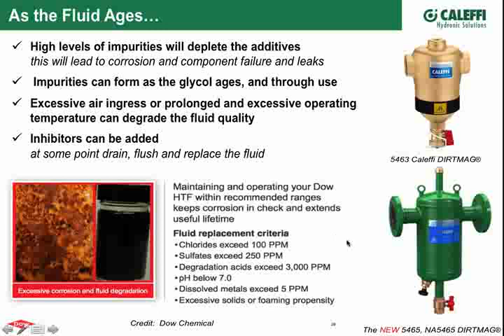This next one is that it's harder to get the air out of a glycol, and this hit home for me. I was at a trade show a while ago, and they had a clear tubing display of an air elimination device. I noticed the fluid was green-colored, and I said, oh, you got glycol in there, don't you? He said yeah, because we keep them in our trucks in the wintertime and don't want this clear display to freeze, so we put a little glycol in there. But he said we got to keep a non-foaming agent in there, because the demo doesn't work very good when we pump air in it to show how the air comes out with this piece of equipment. He said it can take like 15 or 20 minutes for that air to clear out of this little system. Because of the glycol, what is it about it? Am I pulling stuff out of my butt here, does that make sense?